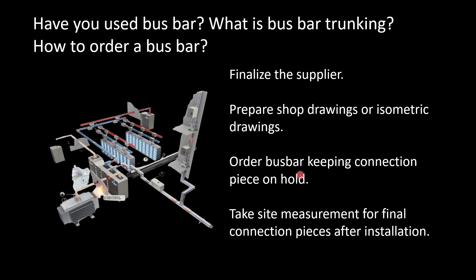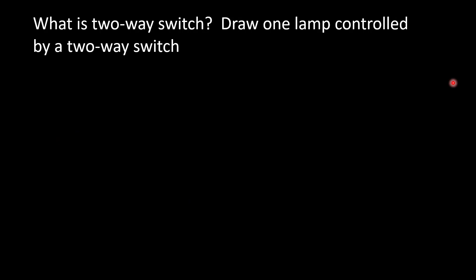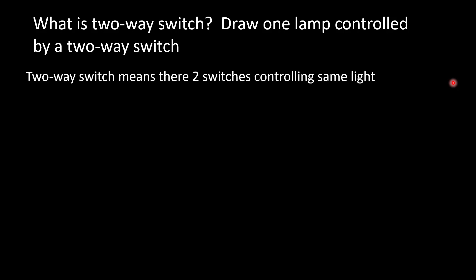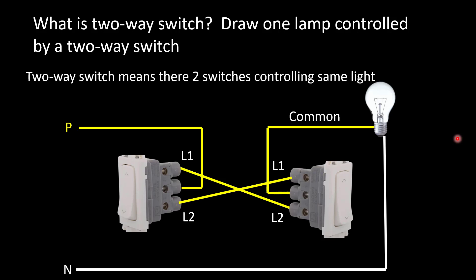What is a two-way switch? Draw one lamp controlled by a two-way switch. If you are applying for a junior position or a position requiring less than five years of experience, you will definitely face this question — it is normally asked to freshers. Two-way switch means there are two switches controlling the same light or same load. For the drawing: the line comes to the common terminal; L1 of the first switch is connected to L2 of the second switch; L2 of the first switch is connected to L1 of the second switch; then the common of the second switch goes to the light, and the neutral returns. This is a typical drawing of a two-way switch.